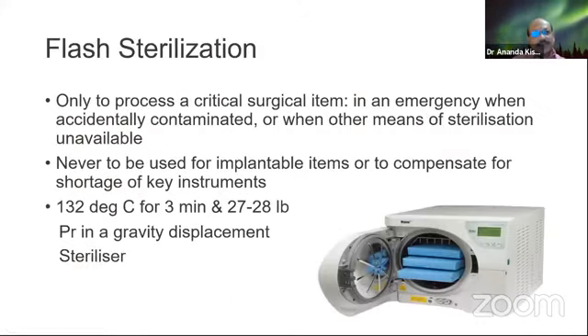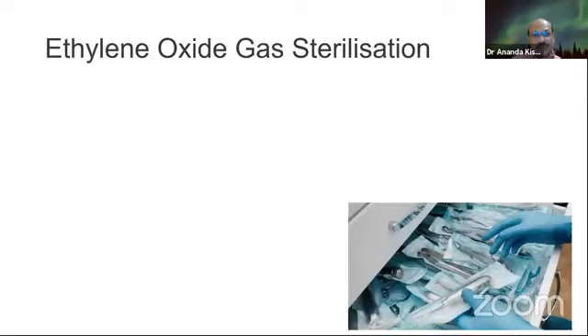Now, flash sterilization. This is only to process critical surgical items in an emergency situation. This is not a standard type of sterilization, never to be used for implantable items or to compensate for a shortage of key instruments. Basically, it is 132 degrees centigrade for 3 minutes, and the pressure is 27 to 28 pounds per square inch. So the gravity displacement sterilization, the flash sterilization, should only be used in a very emergency and critical condition. This is not a standard way of sterilization.